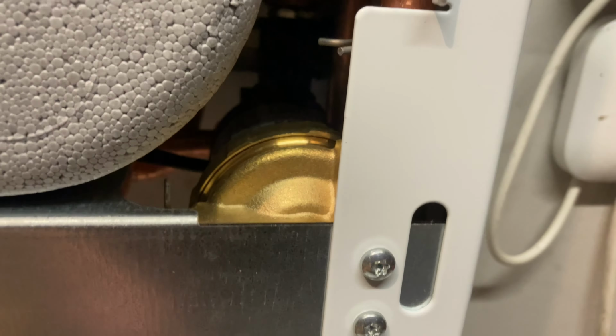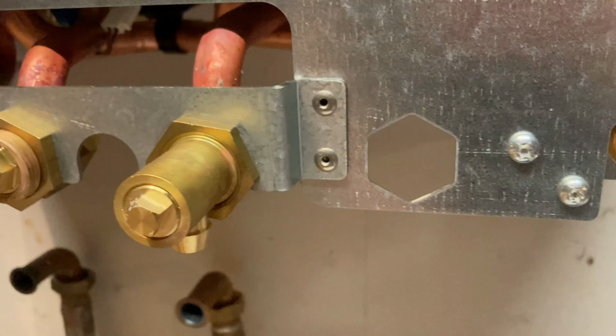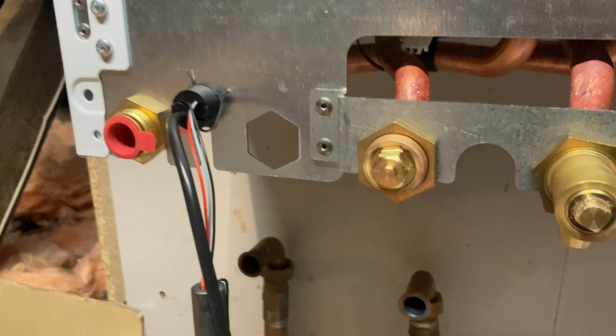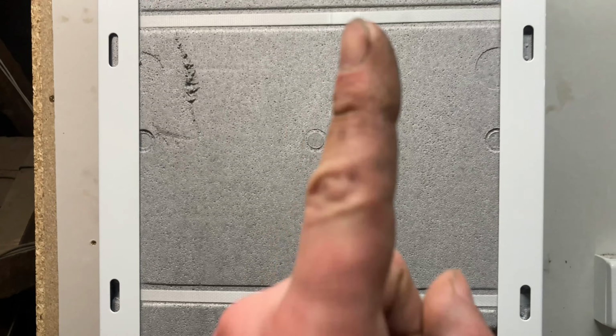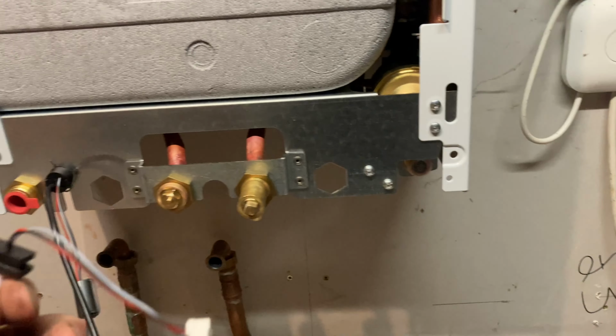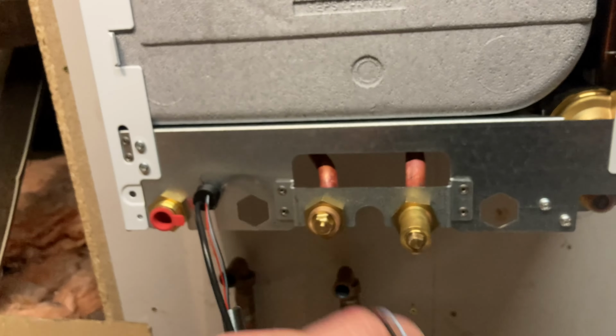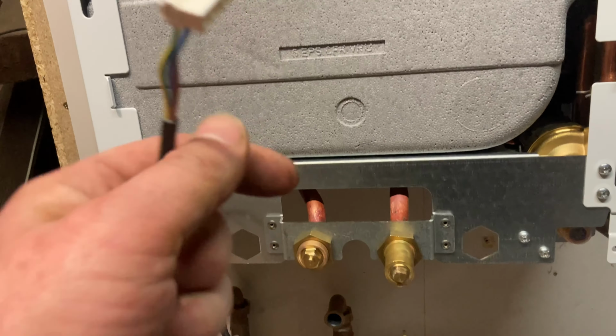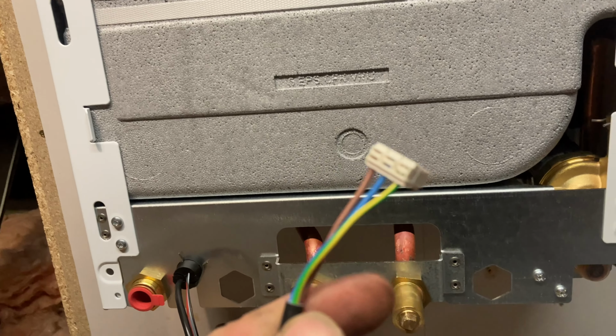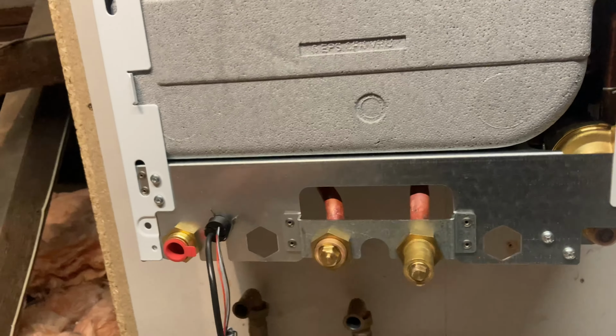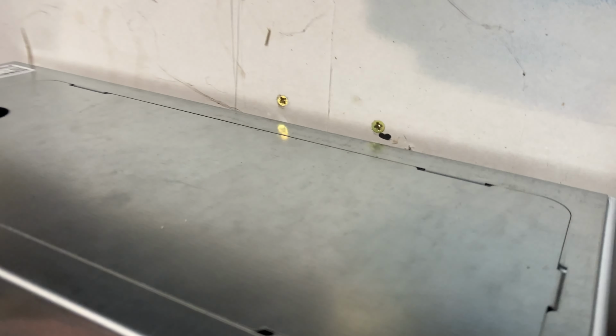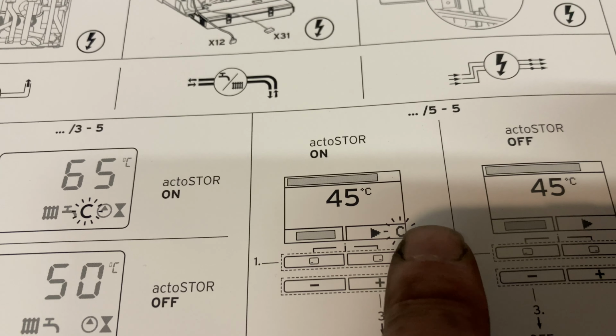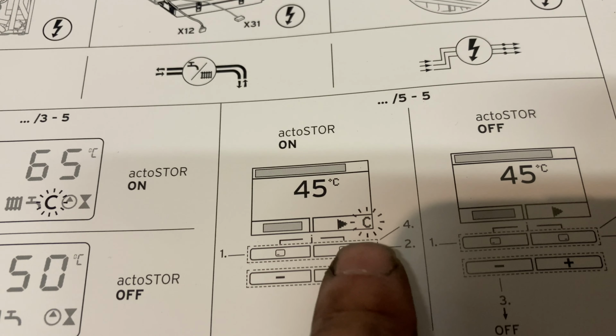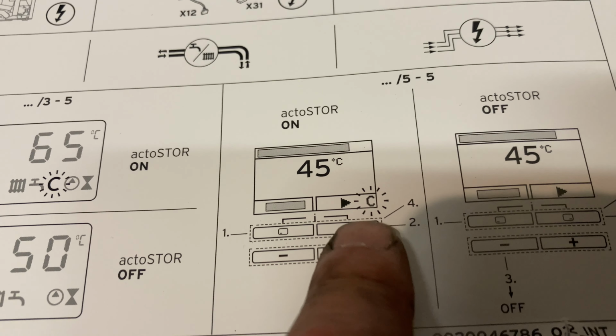That's the low voltage charging pump, 24 volts. That's in the back unit where the 2 cylinders are to charge the water. At the top, it's all insulated. There's 2 cables. One's for the NTC of the cylinder and the other one is for the charging pump. They connect onto the PCB. There's the additional expansion vessel as well for the hot water. For the boiler, always activate comfort mode. That will charge the 2 cylinders at the back of the appliance, giving you 18 litres a minute. If you don't, it'll just function like an ordinary combi.